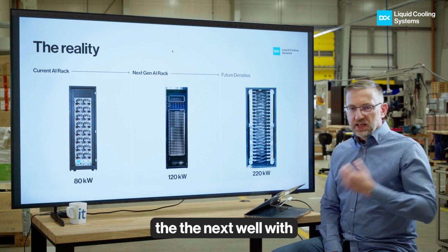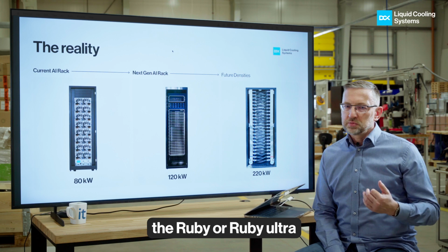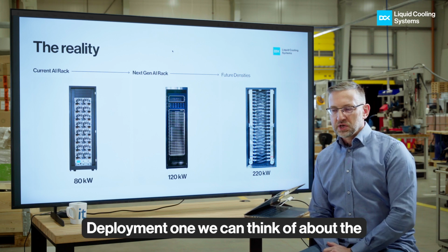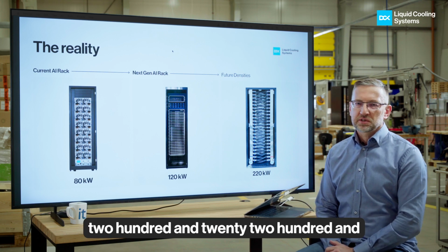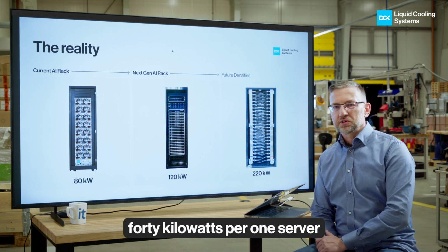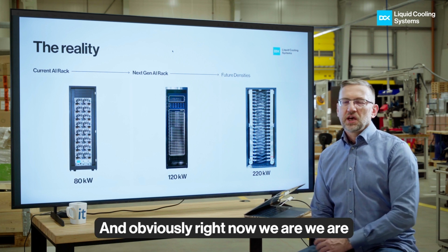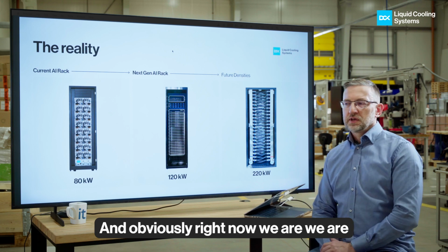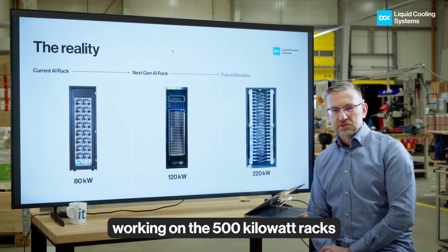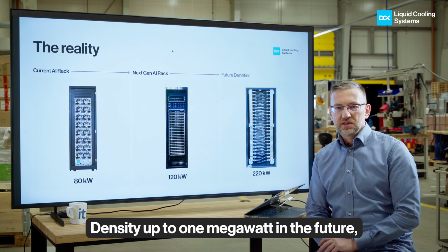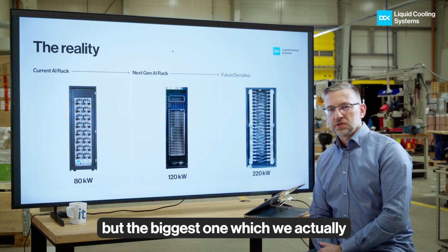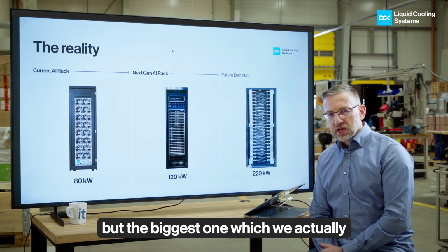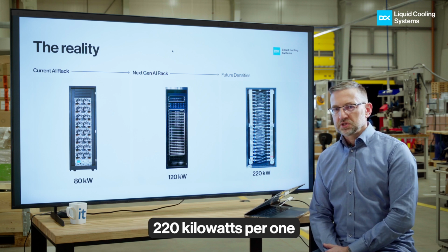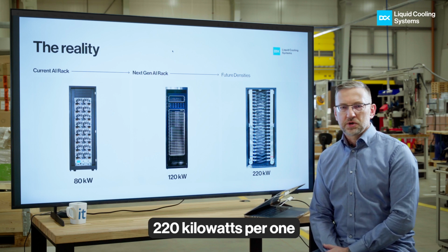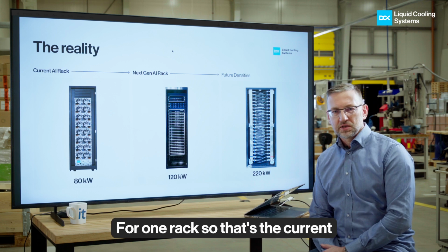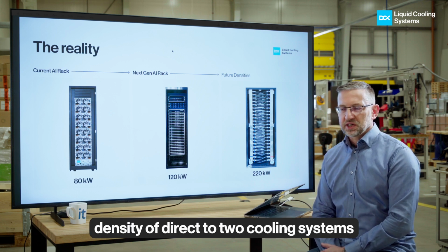And the next, well, with the Rubin or Rubin Ultra deployment, we can think of about 220, 240 kilowatts per one server. And obviously right now we are working on 500 kilowatt rack densities, up to 1 megawatt in the future. But the biggest one which we actually deployed was approximately 220 kilowatts per one rack. So that's, let's say, the current density of direct-to-chip cooling systems.